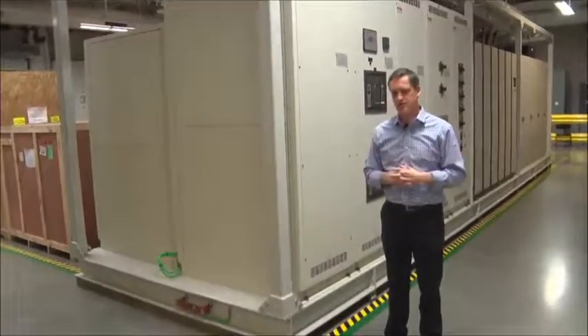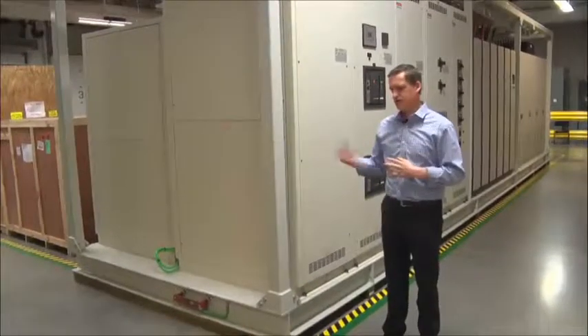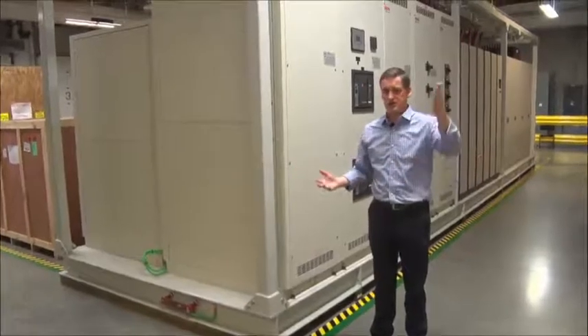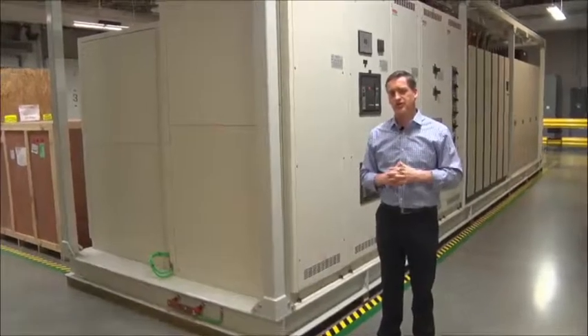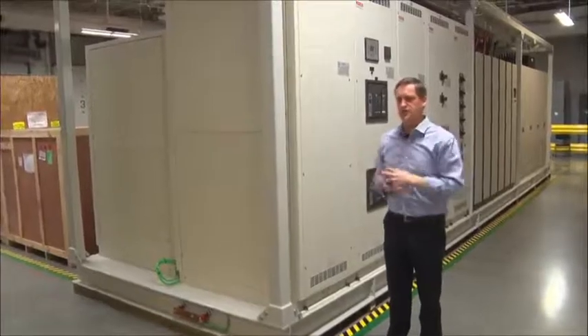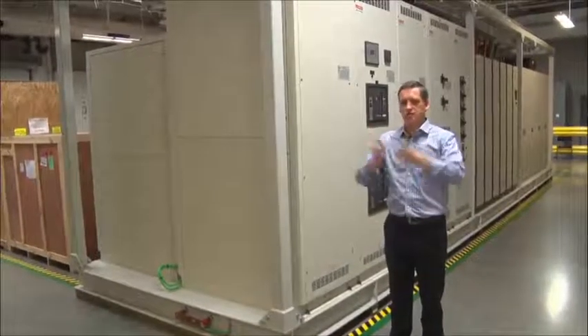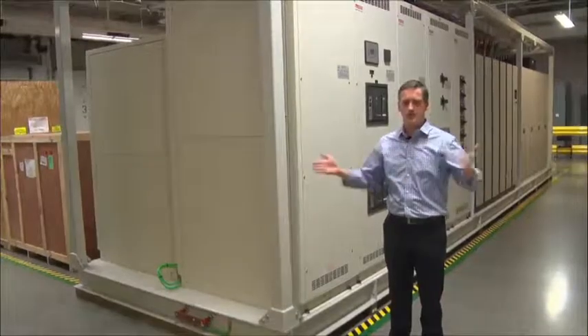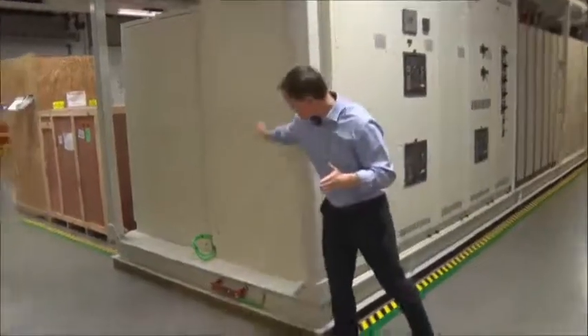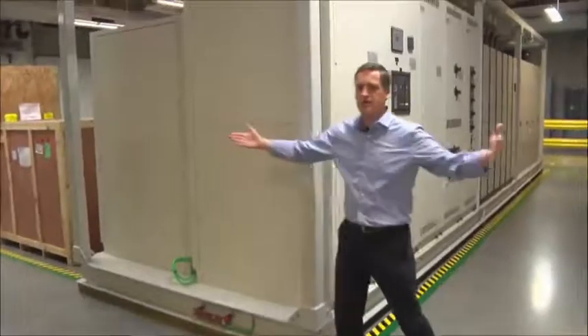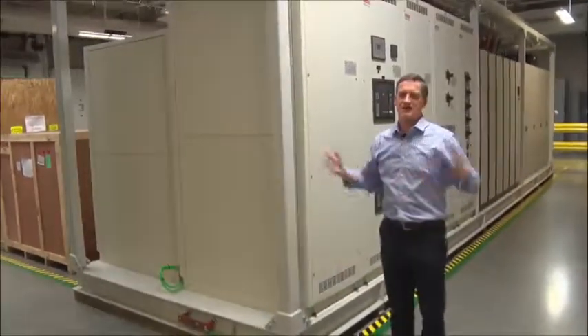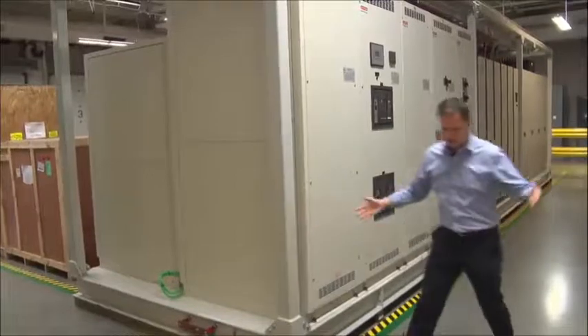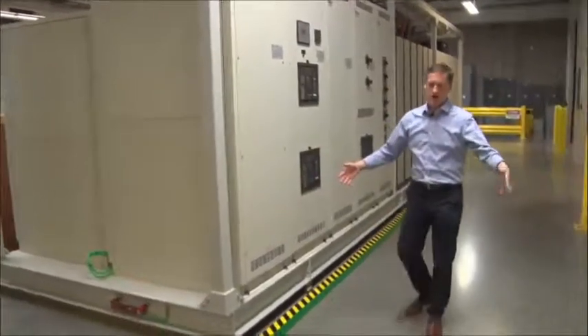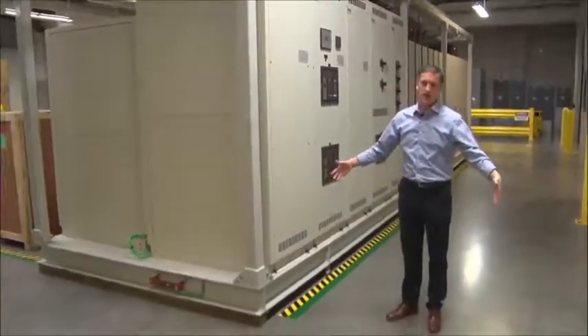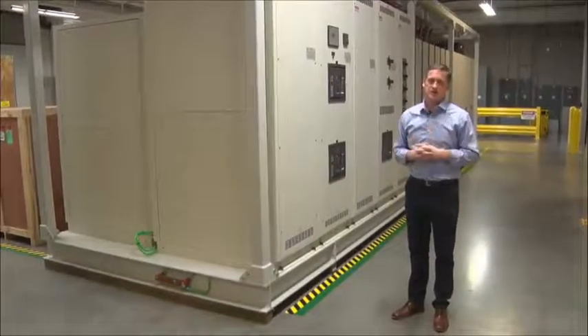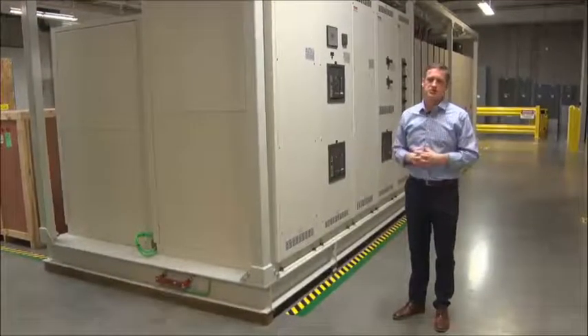So why a power skid versus a module? Like I said, it's more of a preference. A module's difference is that it's designed for an outdoor solution. It's going to be much like the module we were in earlier with the IT racks, but we'll have this equipment instead. That equipment will go against the wall, so we'll have more clearance internally. Instead of having equipment back to back, it will be face to face but along the walls, and that takes up more space. So the module is going to be much wider, probably around 11 to 12 feet wide, even a bit wider than the IT space, in order to meet those clearance requirements.